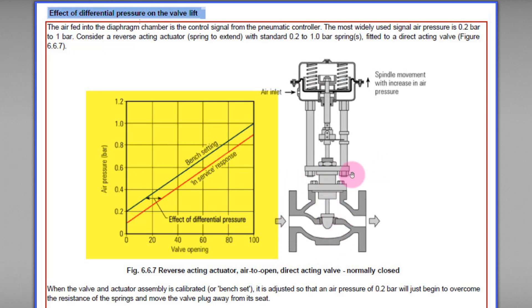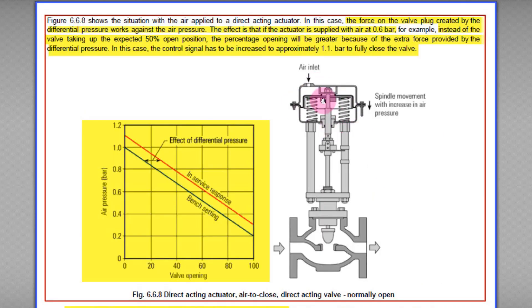Don't be confused about the actuator and the valve body. This part is the actuator and this part is the valve body. When we talk about a control valve, we usually refer to the whole assembly. This is a direct acting actuator — we know because the instrument air is supplied to the top of the actuator.